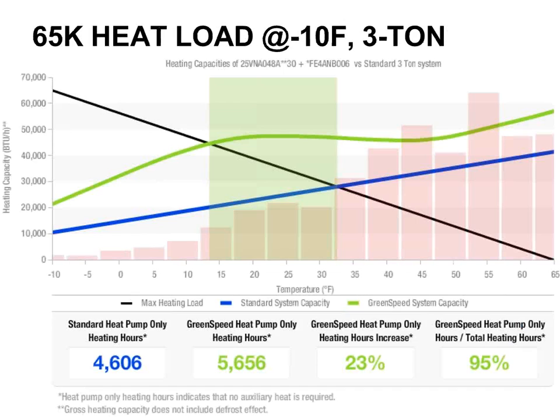Here's just another way to look at it. This is a particular manufacturer's tool that you use to graph things out on a case-by-case basis. It's the same kind of thing though. It goes from -10 to 65 outdoor temperature on the bottom, BTUs up the left-hand column. The black line on an angle is the load of the building or the house. The blue line is if I put in a standard heat pump. The green line is if I put in a variable speed heat pump. The nice thing about this tool is it automatically calculates for you. Everything in this green shaded area is my additional heat pump hours that I normally would not have gotten on a traditional heat pump system, right?